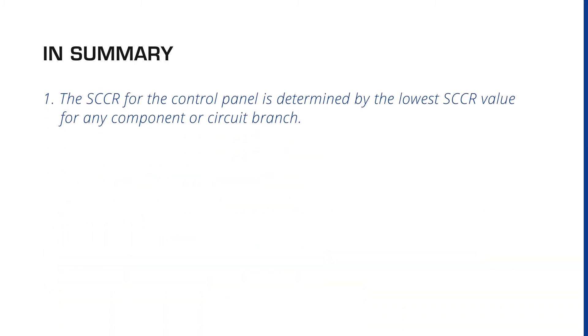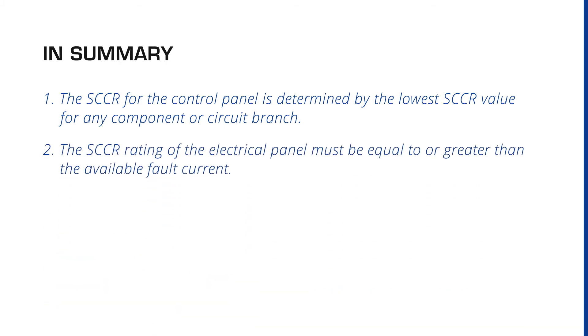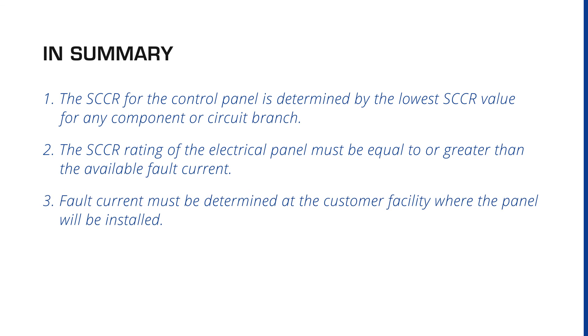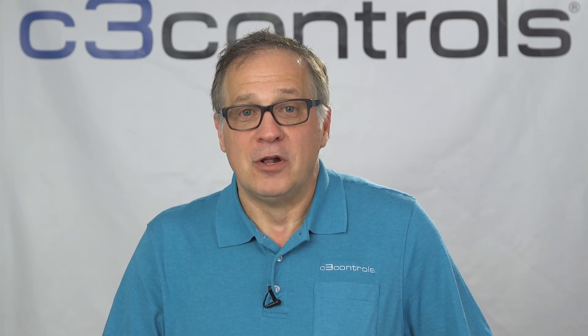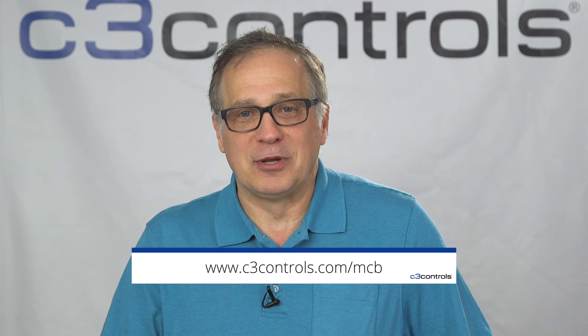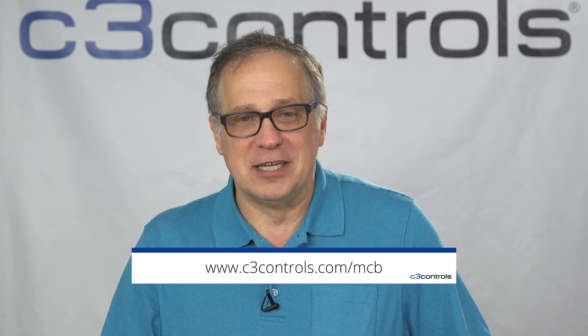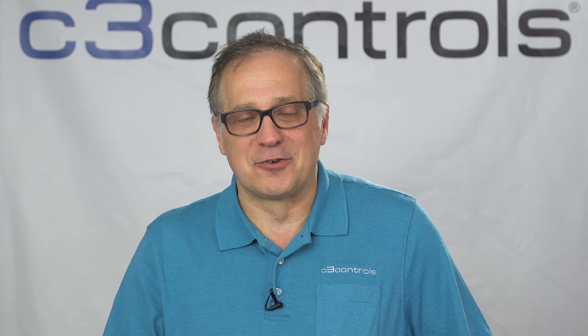To summarize, three things are important to remember when complying with SCCR ratings. One: the SCCR for the control panel is determined by the lowest SCCR value for any component or circuit branch. Two: the SCCR rating of the electrical panel must be equal to or greater than the available fault current. Three: fault current must be determined at the customer facility where the panel will be installed. We here at C3 Controls hope you found this short video helpful. To download a companion white paper and to find other white papers, go to c3controls.com/MCB. Thank you for watching and have a great day from C3 Controls.